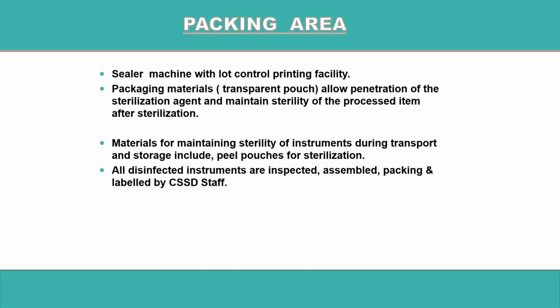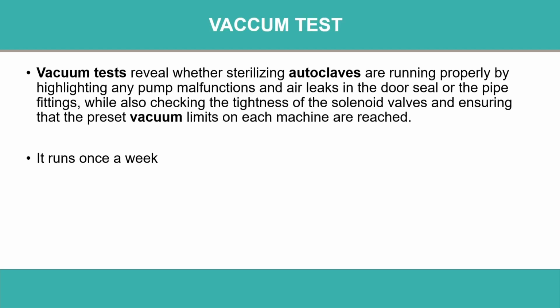These are the packaging area. In the packaging area, we require the sealer machine to seal the reel pouches. We require packaging material that allows penetration of the sterilization agent and maintains sterility of the processed item after sterilization, and material for maintaining sterility of instruments during transport and storage, including peel pouches for sterilization. All disinfected instruments are inspected, assembled, packed, and labeled by the CSSD staff in the packaging area.